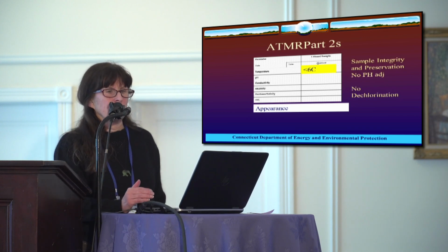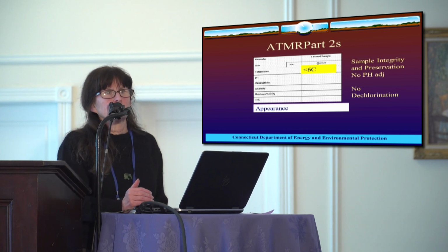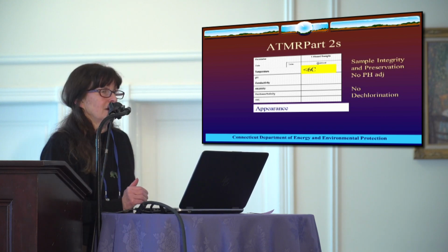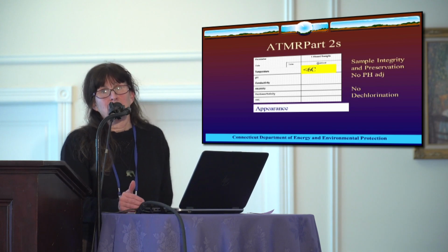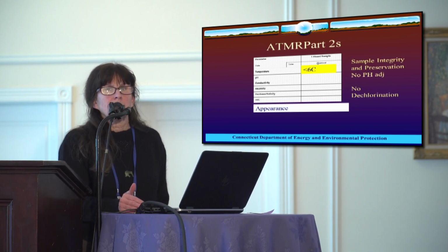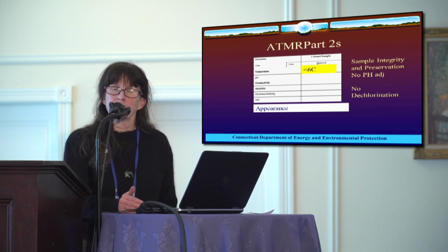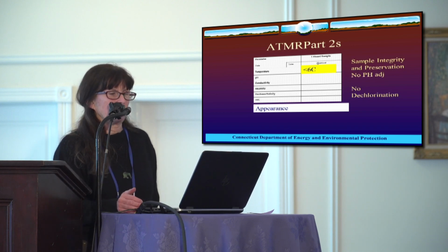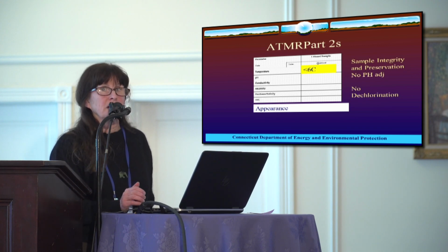And another important thing in this is the total residual chlorine. Occasionally we will get reports on the total residual chlorine for your NPDES monitoring, which is a 15-minute holding time. And then we get the total residual chlorine that the organisms are exposed to, which, if it's a composite sample, could be up to a 36-hour holding time. So a lot of times those two values don't match. And I used to call Kim or the other labs and say, you didn't dechlorinate the sample, because you can't in Connecticut. We also don't allow pH adjustment. So basically the sample coming out of your pipe is the sample that's being tested.